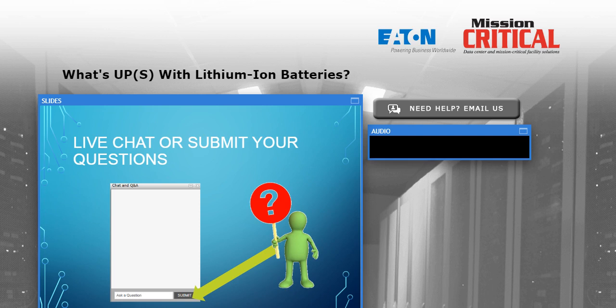If I'm deploying lithium batteries in a storeroom or spare room, there are things I don't necessarily have to do. I don't necessarily need special ventilation at reasonable size levels. I can recycle that ventilated air back into the room, which is something we typically don't do, or aren't allowed to do, with flooded electrolyte batteries. At least at this point, the code hasn't specified anything about explosion-proof lighting fixtures and switches until you get above 600 kilowatt hours, which would be a very, very large number of lithium batteries packed in the same room.